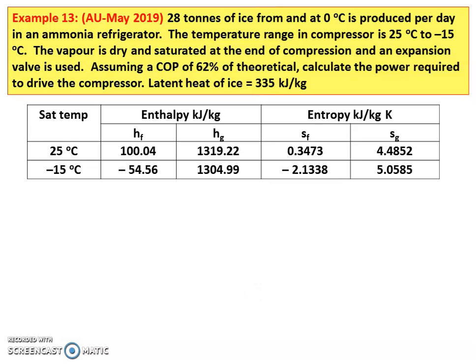Example number 13, from the May 2019 question paper. 28 tonnes of ice from and at 0 degree Celsius is produced per day in an ammonia refrigerator. The temperature range in the compressor is 25 degree Celsius and minus 15 degree Celsius. The vapor is dry and saturated at the end of compression and an expansion valve is used. Assume a COP of 62% of theoretical. Calculate the power required to drive the compressor. The latent heat of ice equals 335 kilojoules per kilogram and the properties of the ammonia refrigerant are given.